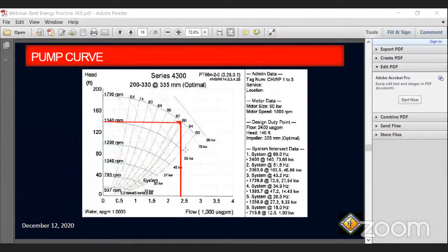This is where over-design happens, the head gets too high, making it inefficient. So if your pumps are centrifugal, you can use a VFD. The system intersection data on the right side, at 2400 GPM and 140 feet design, that is 73.68 kilowatt. But if you want to lower your frequency, the flow goes down, then the head goes down too. So you still save, 46.86. That's the play you get when you use the VFD, adjusting the flow and the head.